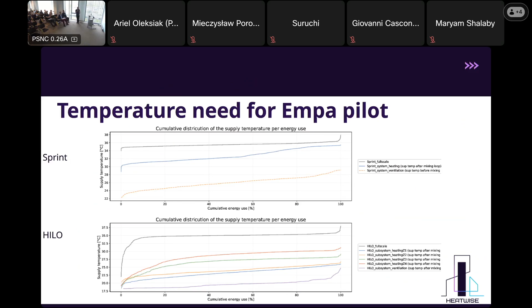So if we try to summarize the findings for the buildings we have analyzed, and what we see in many buildings in Denmark, ventilation normally never goes above 50 degrees. Also, if you heat the air more than 53, you start burning the dust and get a bad smell, so for many reasons you would not like to go that high. Typically it's 25 to 35 degrees, and rarely above 40.